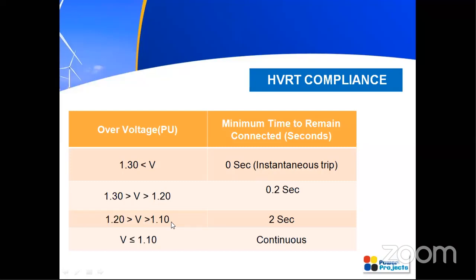Okay. But if the over voltage increases from 1.1 per unit to 1.2 per unit, your wind farm has to remain connected for 2 seconds. This is the minimum time it has to remain connected with the grid. And if your voltage varies from 1.2 per unit to 1.3 per unit, that is, it goes still higher, it is sufficient to remain connected for 0.2 seconds. Okay. If the voltage increases above 1.3 per unit, you can go for instantaneous trip of your wind farm. This is a very important mandatory condition for HVRT. So your wind turbine has to ride through this high voltage. This is about the HVRT compliance.